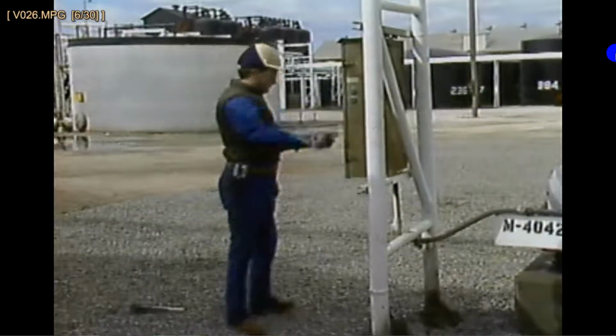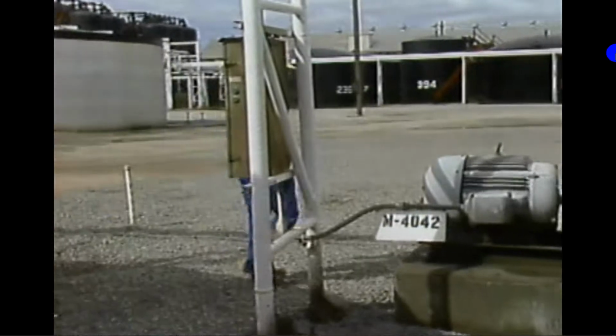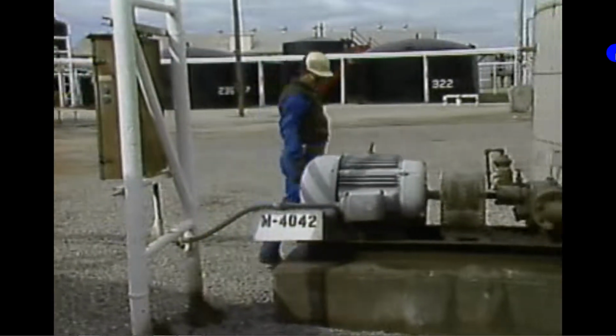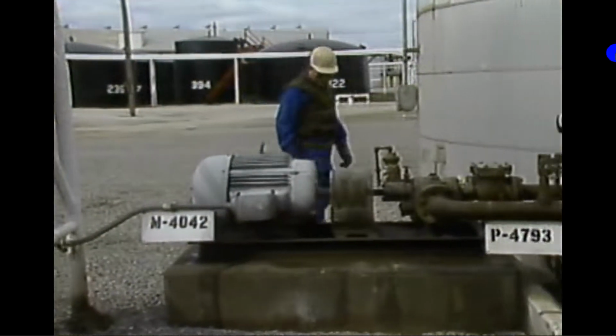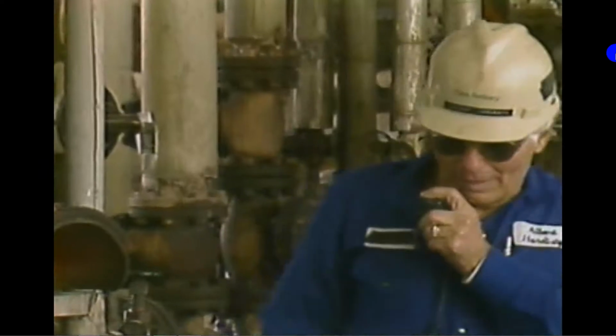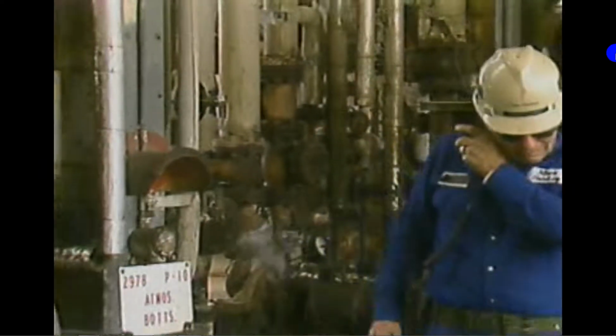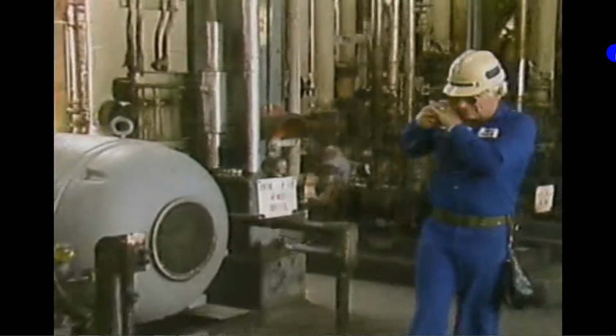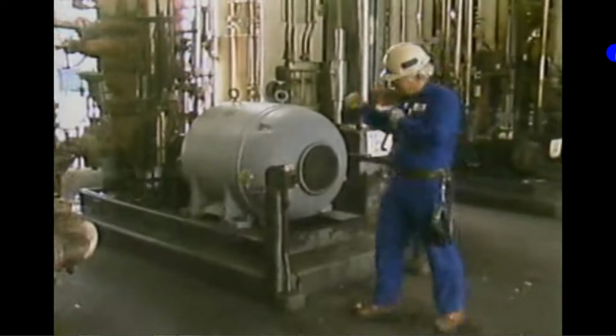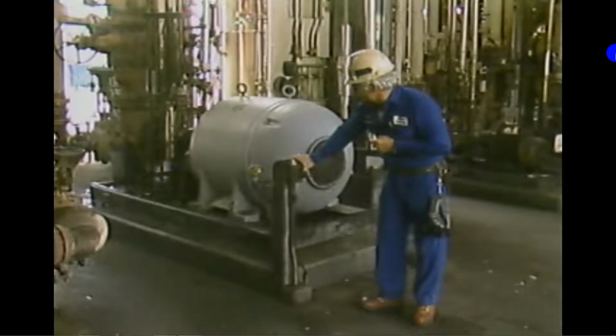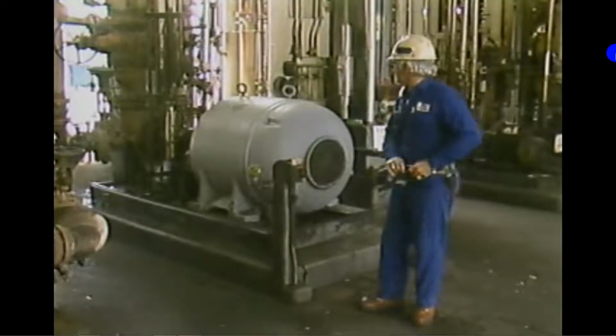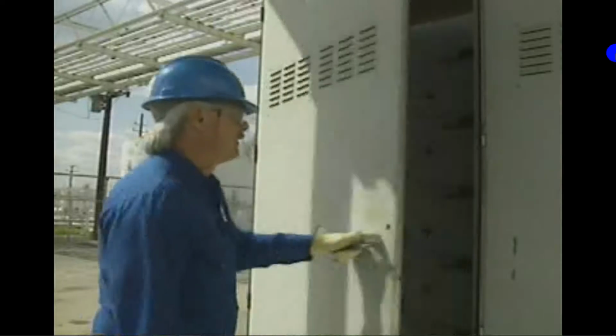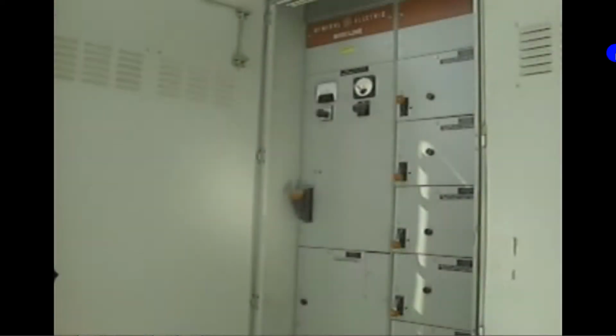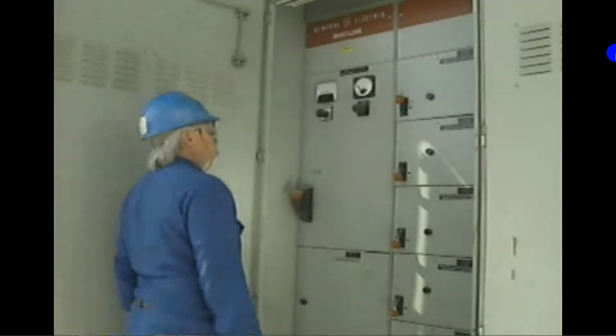An operator must be at the location because the push button or switch of a manual controller directly controls the flow of current from the power supply to the motor. A manual controller is usually located near the motor it operates. This way, an operator can make sure that the equipment is operating properly and can take action to correct any problems that occur. Another common way that an AC motor can be controlled is by using magnetic controllers.